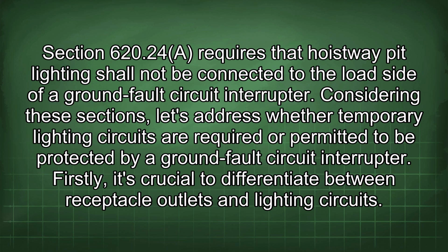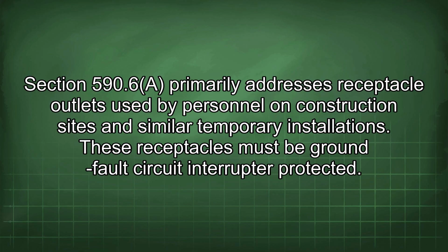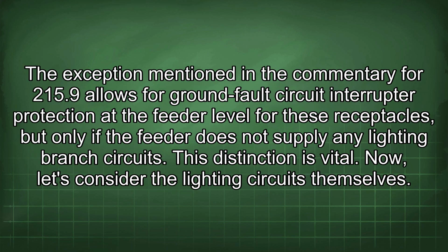Considering these sections, let's address whether temporary lighting circuits are required or permitted to be protected by a ground fault circuit interrupter. Firstly, it's crucial to differentiate between receptacle outlets and lighting circuits. Section 590.6 primarily addresses receptacle outlets used by personnel on construction sites and similar temporary installations. These receptacles must be ground fault circuit interrupter protected. The exception mentioned in the commentary for 215.9 allows for ground fault circuit interrupter protection at the feeder level for these receptacles, but only if the feeder does not supply any lighting branch circuits.